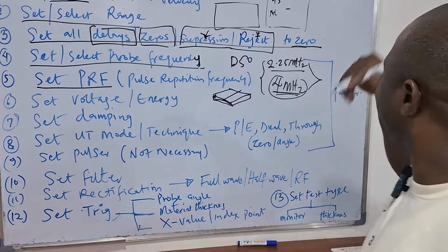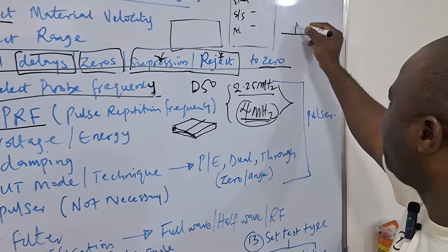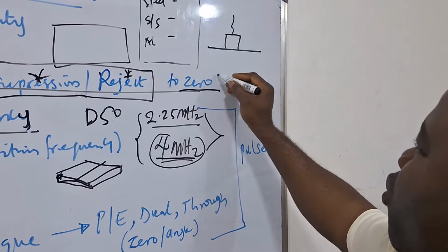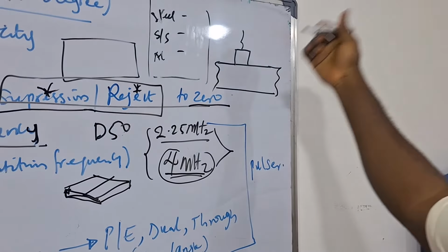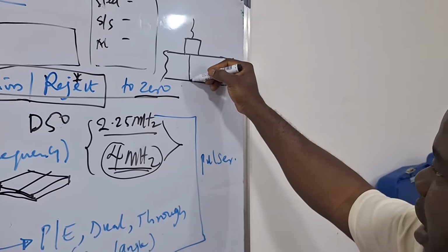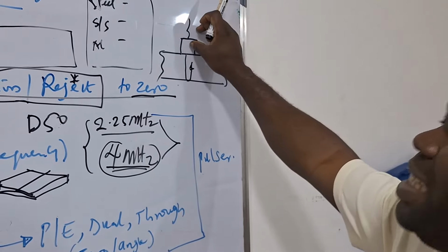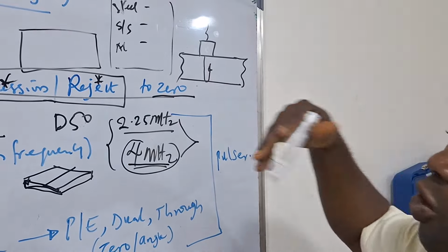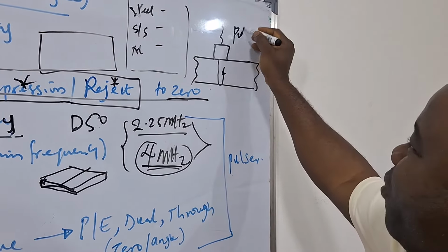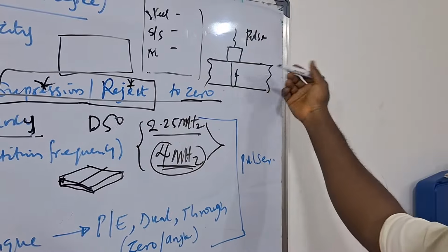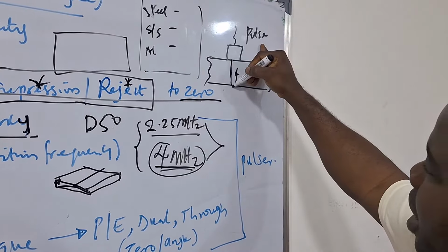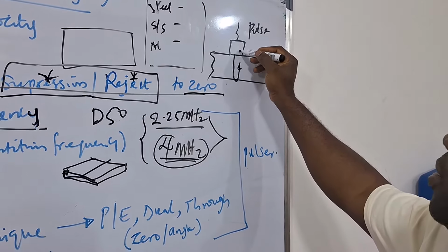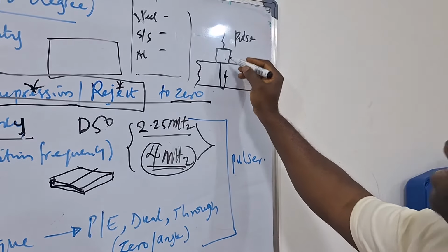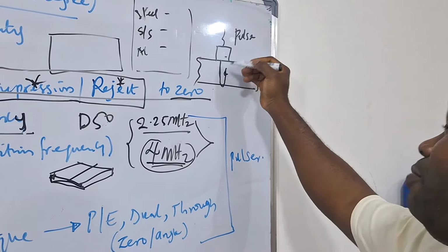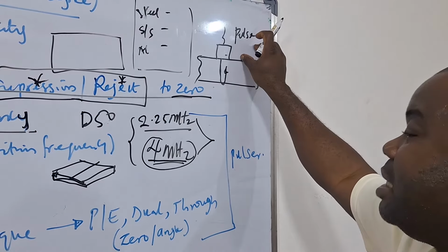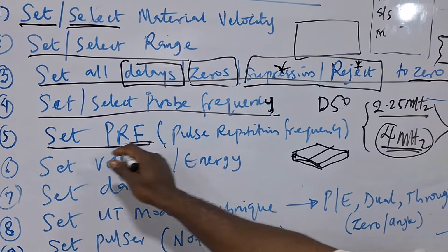So remember the concept of PRF is this. Let's say we have a probe, a 0-degree probe, and we have a material. Say this is the material. How it works is it sends this ultrasound signal, it hits the back wall and comes back. Now, the UT signal is not a continuous signal. That means it does not move continuously. Rather, it pauses, so it sends in the form of pulses. This is just an illustration. So the idea is if you send in a UT signal, it goes in and comes back with the reflected echo. The next one goes. Let's say I send 3 pulses, the time interval between each of these pulses will be determined by your PRF.